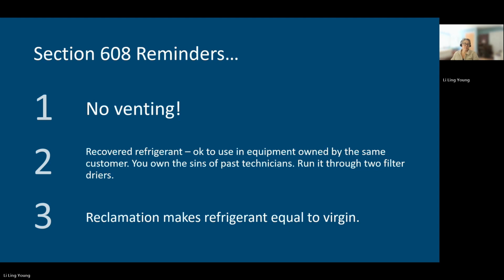Recovered refrigerant. If you recover refrigerant, it's okay to reuse it in equipment that's owned by the same customer where you recovered the refrigerant. But if you do so, whatever happened to that refrigerant and that equipment before you recovered the refrigerant, now you own it. If the refrigerant is not in good condition, that's now going to impact the equipment that it goes into. So at a minimum, run that refrigerant through 2 filter dryers. And finally, reclaimed refrigerant makes refrigerant that is at least as pure as virgin refrigerant.